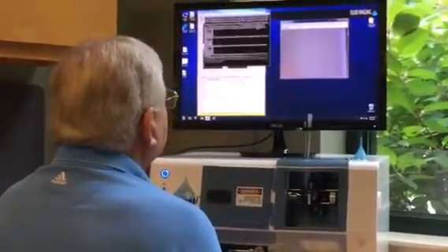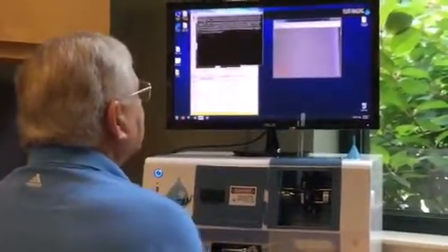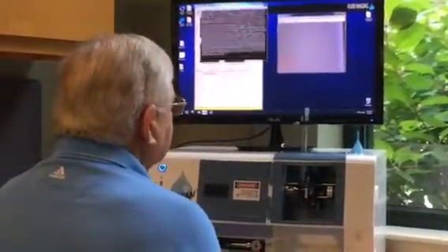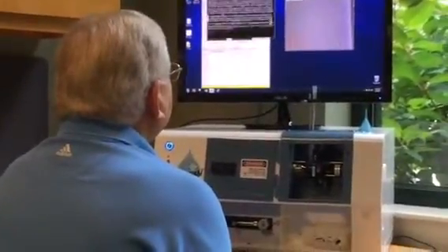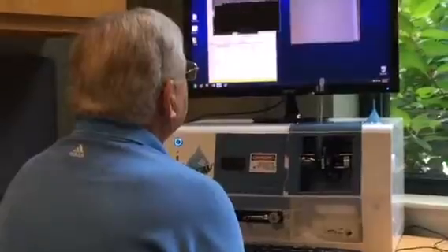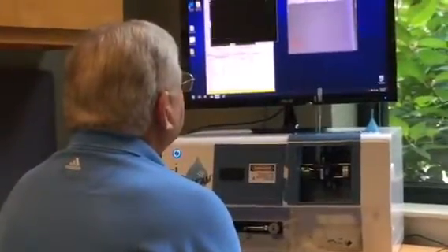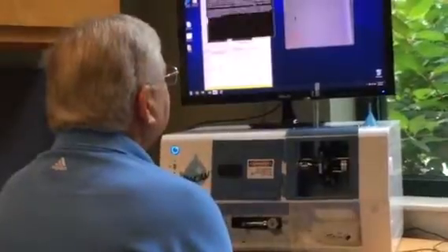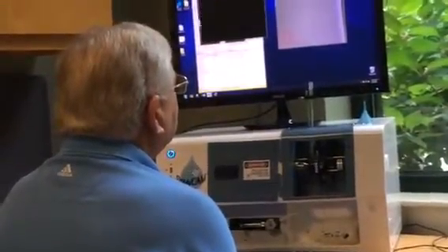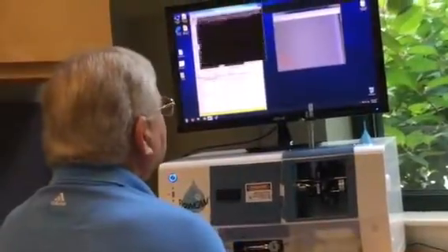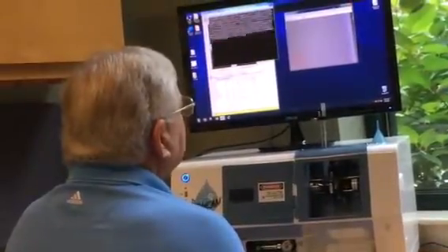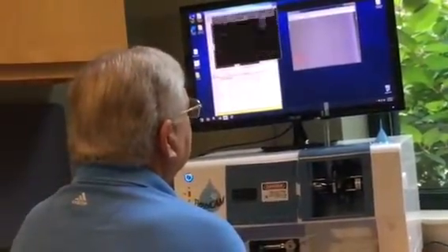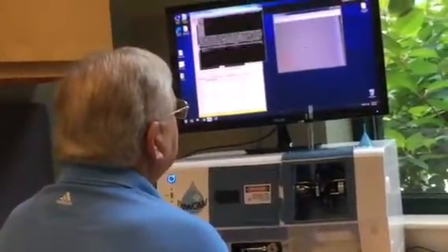That stops at 2 liters, right? It will stop at 2 liters. I think I set it for 1. Yep, automatically. Wow. Big chunk. Bingo. So the big chunks are a little tricky because they have a very different flow rate, and so you'll see that occasionally you get duplicate images of them. So just keep an eye out for that when you're doing your counts. You have such a low number of them relative to the other particles that it's not going to have a drastic effect on your data.